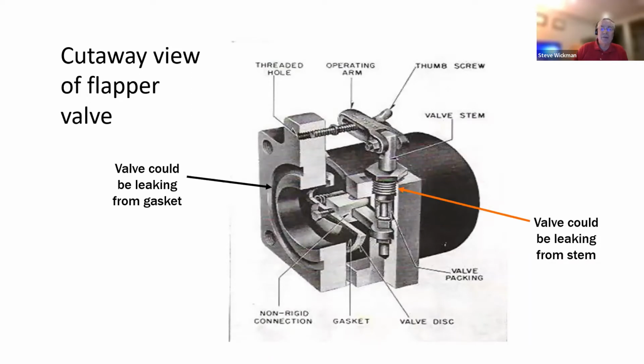Here's a cutaway view of one of those flapper valves. That was where we were doing the drill and inject. And actually, the next slide kind of shows this too. But you can see the black arrow is pointing to that gasket groove that we're going to locate and drill into. And in addition, we can also drill and inject the sealant compound into the valve packing area. Because sometimes you'll get the packing on these beginning to fail. And we can inject into there to contain the leaks. And the sealant is flexible enough that it's not going to disable the functionality of your valve, as you'll still be able to operate it.